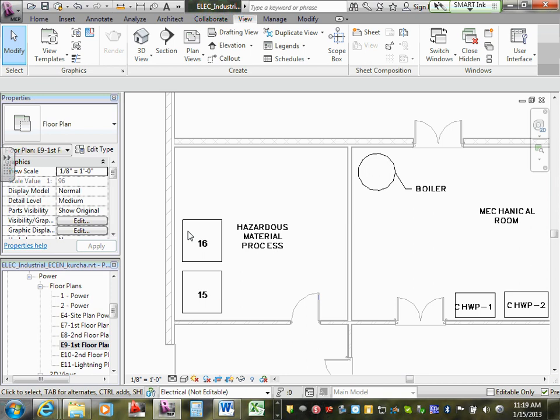It's fully sprinkled in here. So again, they call out for putting in a smoke detector. It's a very expensive piece. The owners will typically come back and say no, we don't want that in there. But again, the horn and the strobe are going to be intrinsically safe, separate systems. You're going to have one beacon and one horn. And that should come here.